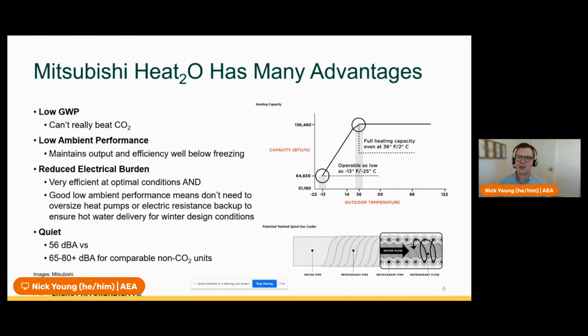The Heat2O units are also really quiet compared to some of the other large capacity central heat pump water heating products on the market. They're rated at 50. I see some cut sheets saying 56 decibels, others saying 60. Either way, that's the lowest number I've seen for a unit of this capacity. Other non-CO2 units are anywhere from 65 to 80 dBA, which can be pretty loud.